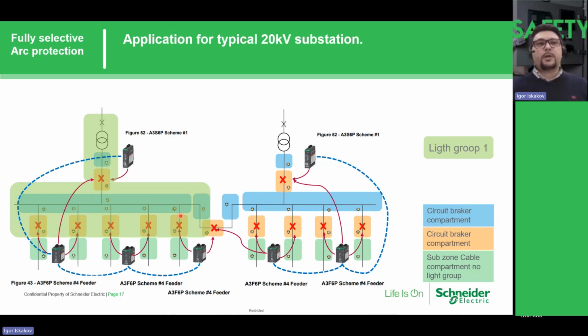So for example, if we have an arc flash here, some of the sensors are dedicated to light group 1, which you can set up using the configuration DIP switches on the device. So the devices will know they belong to light group 1, and during any detection by these sensors dedicated to light group 1, we will have a trip to our incomer and bus bar coupler. This means that the other part of our substation will be secure and working without any stopping.